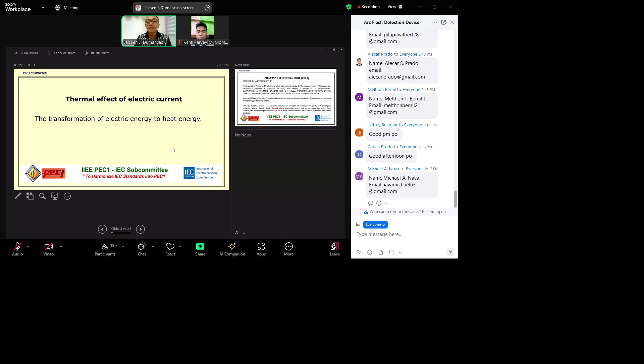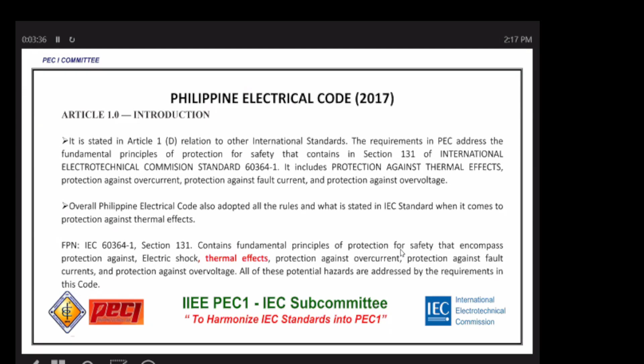Let's take a look at the Philippine Electrical Code. In Article 1, the introduction states, in relation to other international standards, that the requirements in the PEC address the fundamental principle of protection for safety contained in section 131 of the IEC code, which is IEC 60364-1. It includes protection against thermal effect, protection against fault current, and protection against overvoltage. Overall, the Philippine Electrical Code also adopts all the rules stated in the IEC standard when it comes to protection against thermal effect.